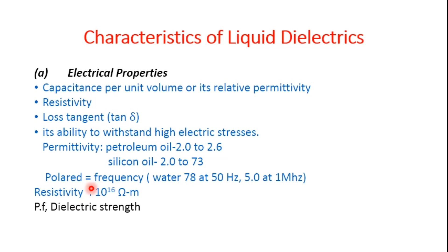The resistivity of liquid dielectric media should be more than 10 to the power of 16 ohm-meters, and most liquids in a pure state exhibit this property. The power factor of the dielectric under AC determines its performance under load conditions. It is more important in the case of cables and capacitors; however, in the case of transformers the dielectric loss is negligible compared to copper and iron losses. Pure and dry transformer oil has a very low power factor varying around 10 to the power of minus 4 at 20°C and 10 to the power of minus 3 at 90°C at 50 Hz.